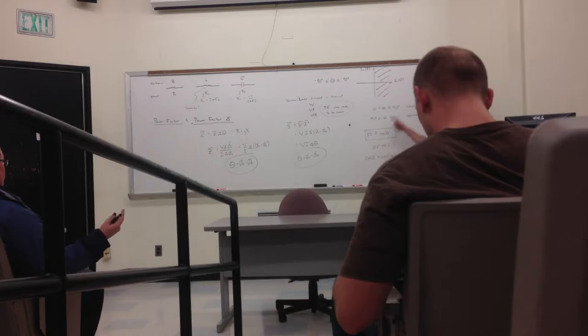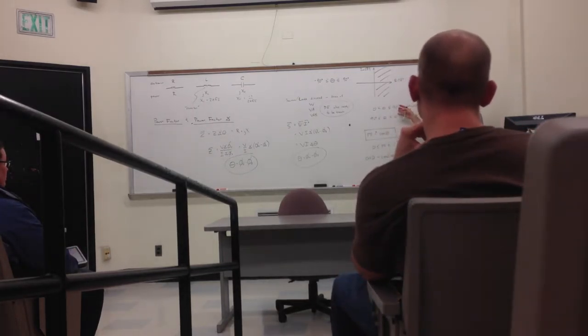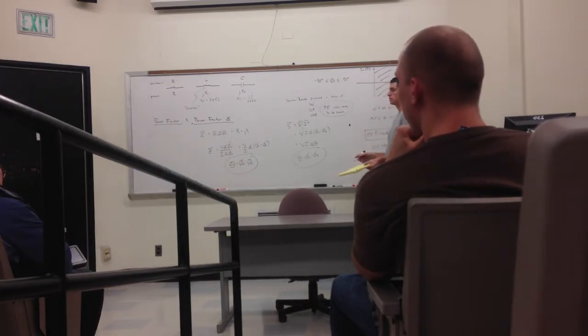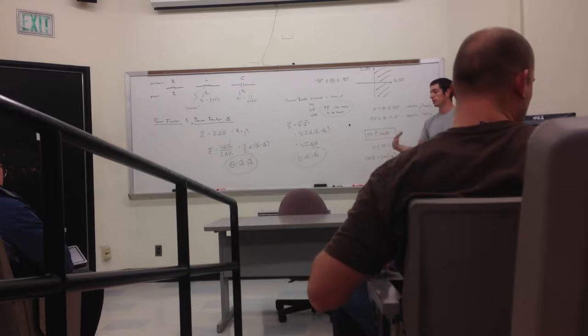So power factor: if I throw in minus 45 degrees, I'm going to get 0.7. If I put in 45 degrees, I'm also going to get 0.7. So this is really important when talking about power factor, you have to discuss it in terms of whether it's leading or lagging. I've also seen it where they give you just a positive number, but they'll actually tell you it's a lagging or leading power factor.